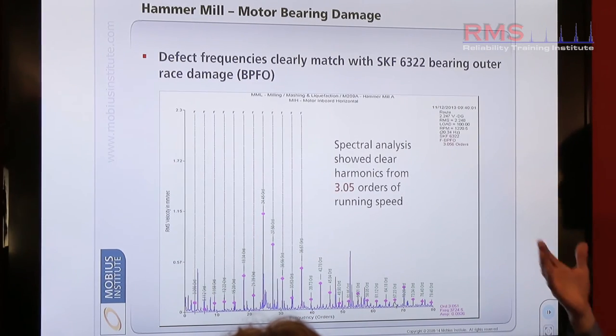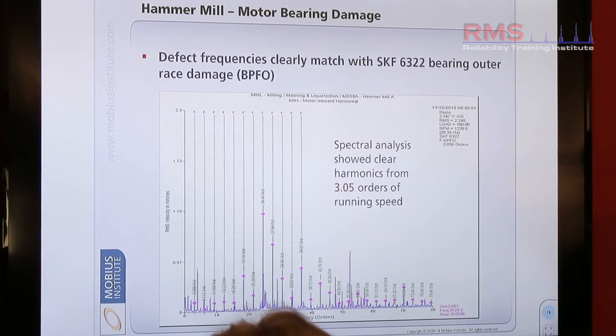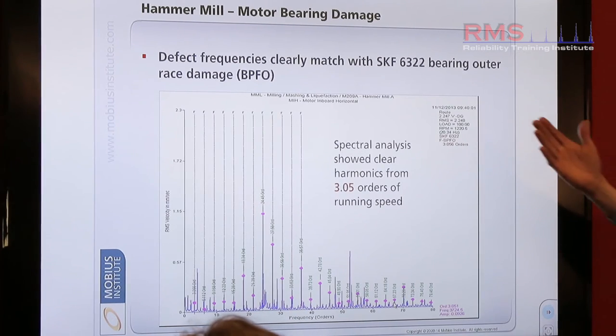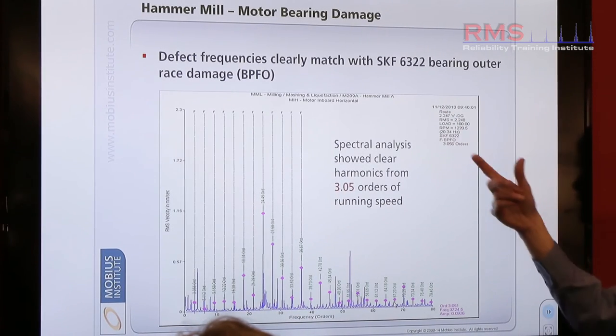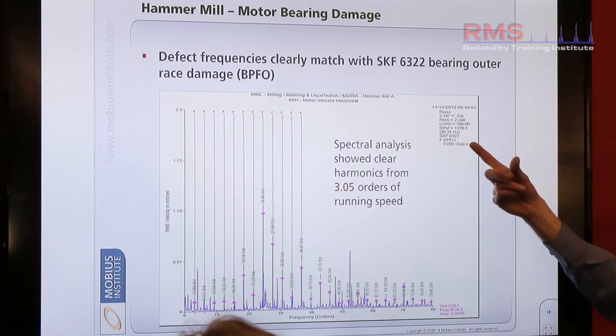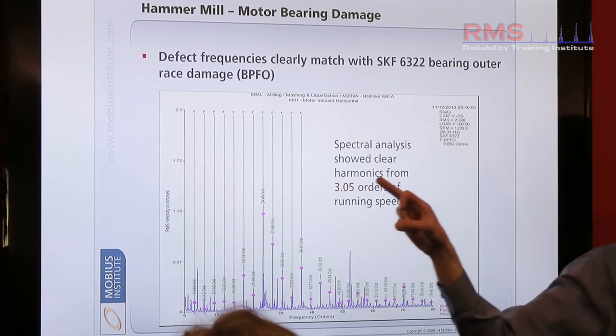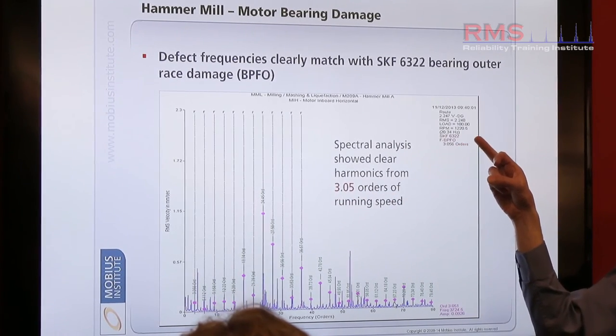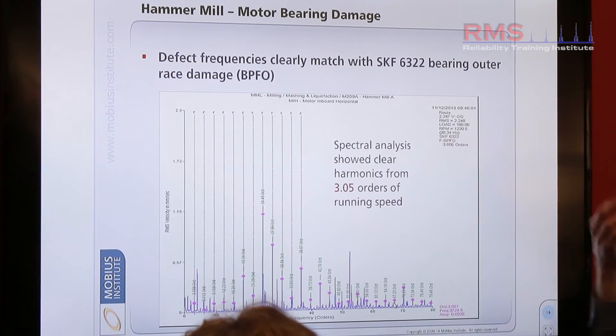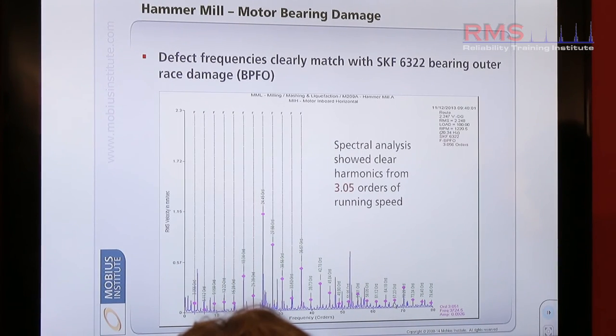In this particular case, the bearing was known — we knew it was a 6322 bearing. And in that case, that correlated with the dotted lines that matched the outer race frequency of the bearing. So we knew exactly that it was the outer race of the bearing.